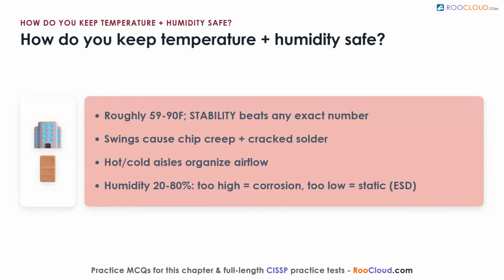How do you keep temperature and humidity in a safe range? By steady control, not just cold air. Equipment rooms generally sit between about 59 and 90 degrees Fahrenheit, but stability matters more than any exact number because swings expand and contract components. That oscillation causes chip creep, where seated chips slowly walk out of their sockets and can crack solder joints.